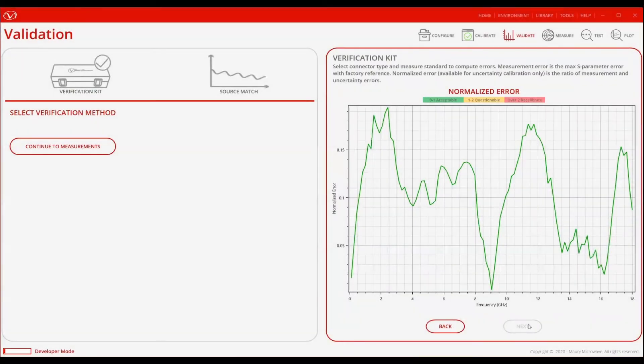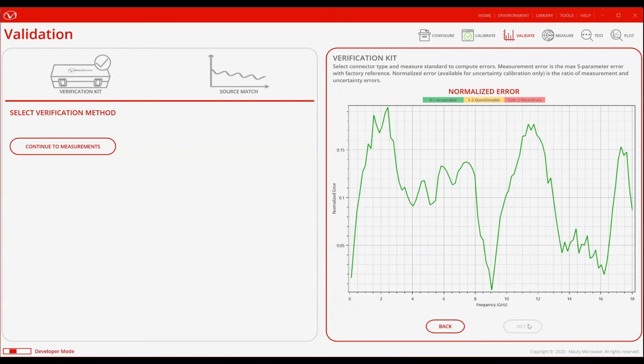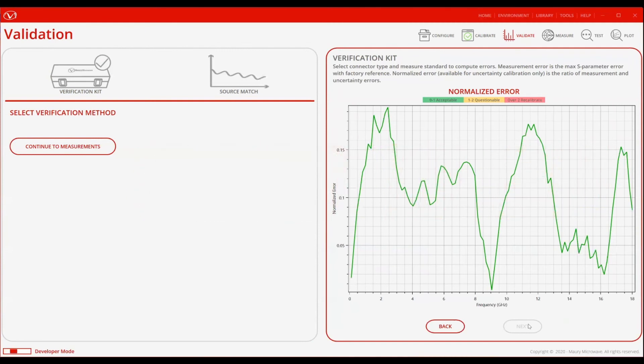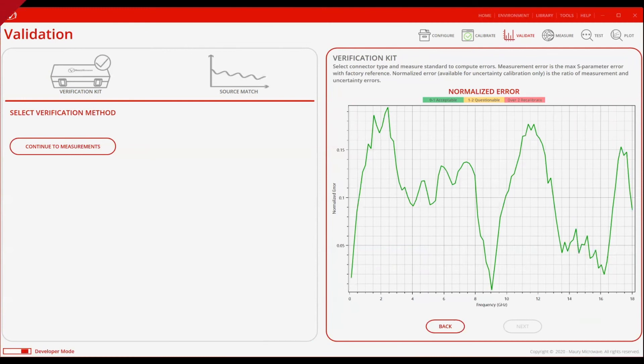One of the biggest benefits of enabling uncertainties is the pass-fail criteria. This graph will tell you whether you are good to go, or you need to go back and recalibrate. If your normalized error is less than one, you are good to go. Between one and two, you may want to reconsider recalibrating, and anything over two, don't take the chance, just recalibrate. In my case, the normalized error is lower than one, so we are good to start measuring our DUT and have confidence that the results will be accurate.